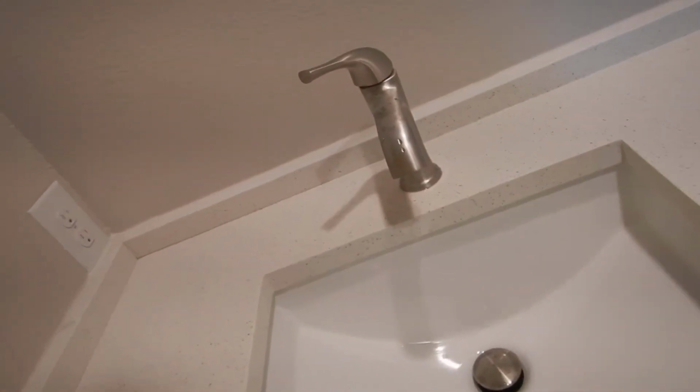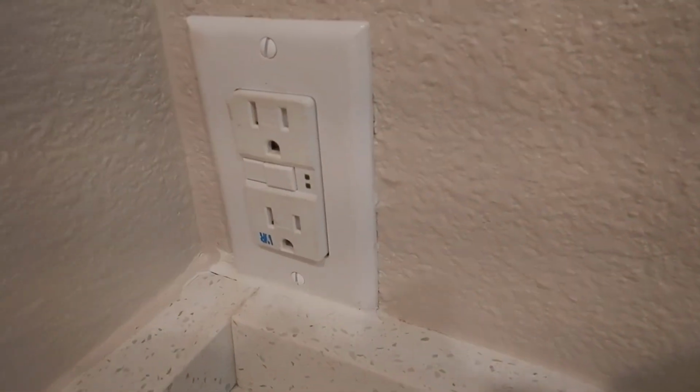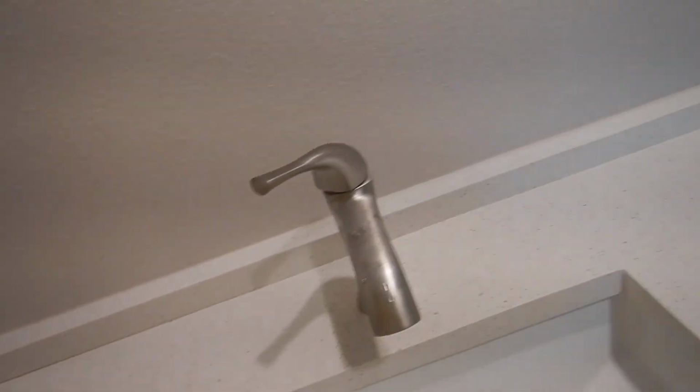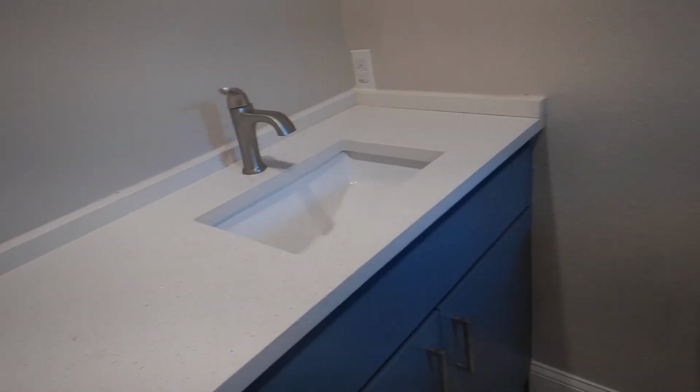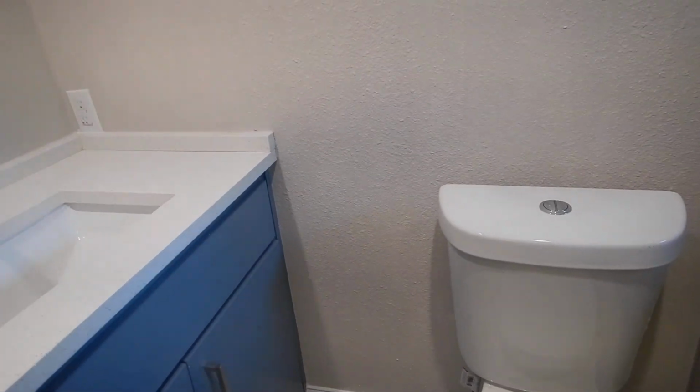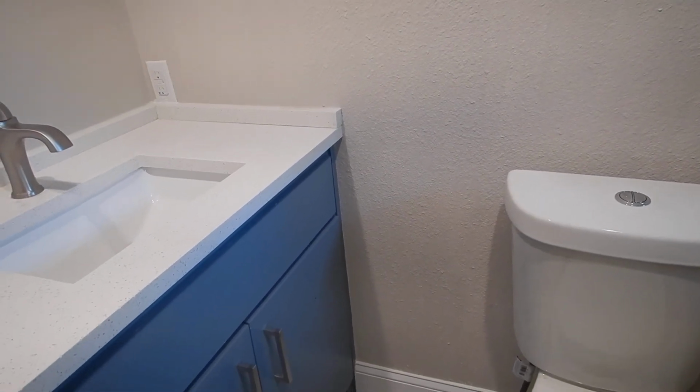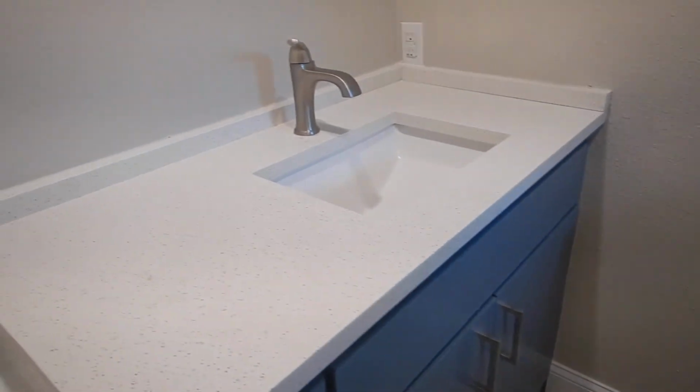This is the primary bathroom. And when I got here, I found this GFCI to have been tripped, and this GFCI is inoperable. I've reset all of the breakers. I tripped the GFCI in the other bathroom and in the kitchen, in the exterior, in the garage. Everything was able to be reset.